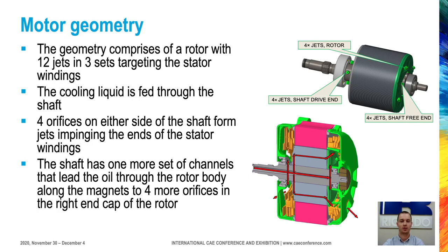To make clear what we are talking about, let's have a look at the geometry of the motor we were investigating. There are three sets of nozzles of 4, so 12 nozzles in total: 4 on one side and 8 on the other side. Looking at the cross-section, we have oil fed from the left side through the shaft. There is a first set of 4 nozzles here, then channels through the rotor going to the other side with another set of 4 nozzles on the right side — so 8 jets for the right side and 4 jets for the left side.